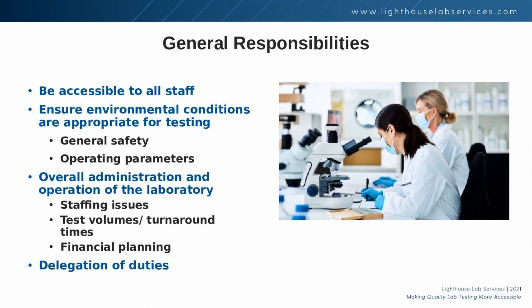The lab director is also responsible for ensuring environmental conditions are appropriate for testing. This really covers two separate requirements, with the first being general safety. It's important that there is adequate space and ventilation and that safety precautions are in place so that laboratory personnel can perform their jobs with minimal risk. The second part is that environmental conditions are required for meeting the operating parameters for instruments used within the laboratory. At bare minimum, this includes temperature and humidity checks.